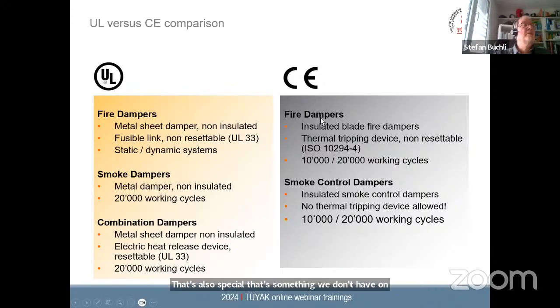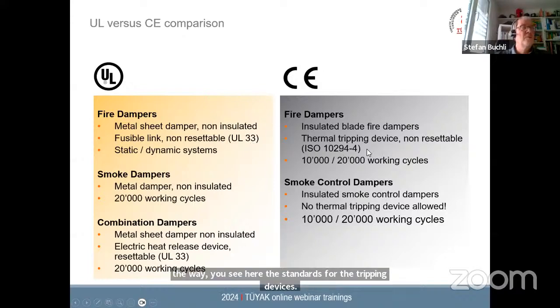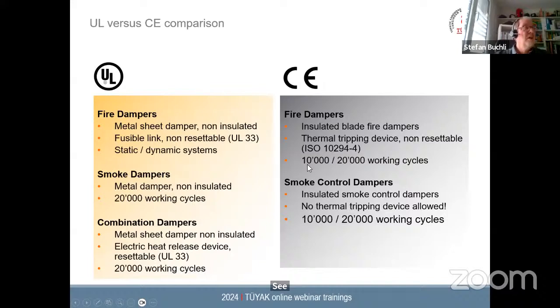You see on the European side, fire dampers, most of the dampers are insulated blade dampers. The tripping device is non-resettable as well. By the way, you see here the standards for the tripping devices. It's UL 33, and on the European side is the ISO standard. What's also special is here on the cycles. Cycles for fire dampers is 10,000 cycles or 20,000 cycles, depending a little bit on the application.